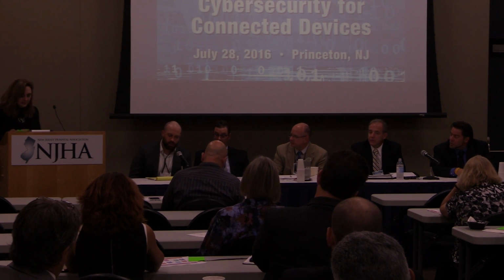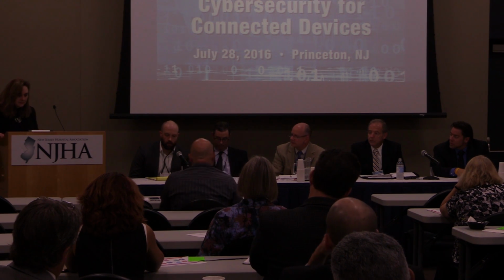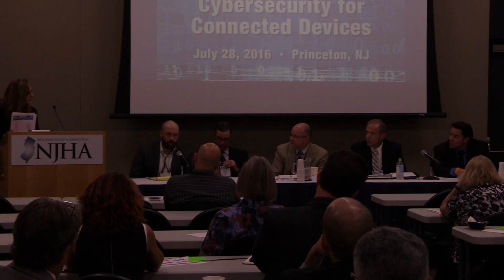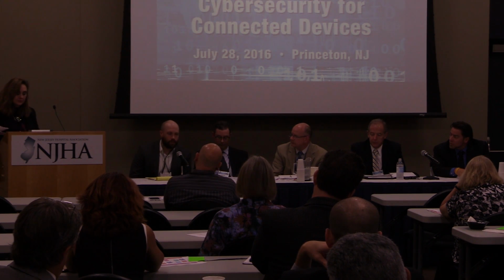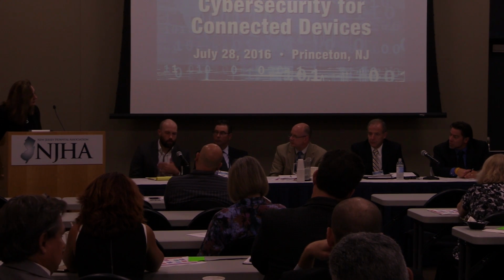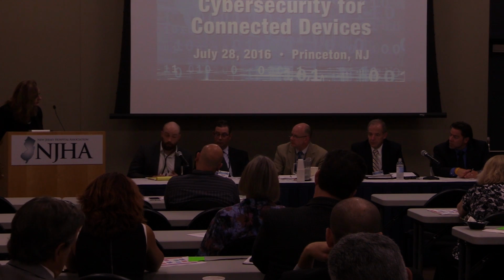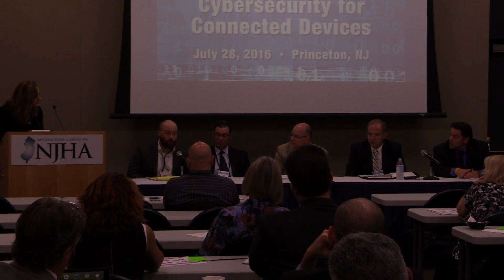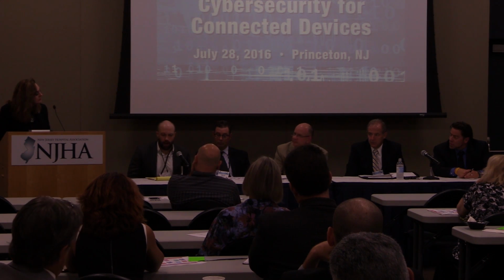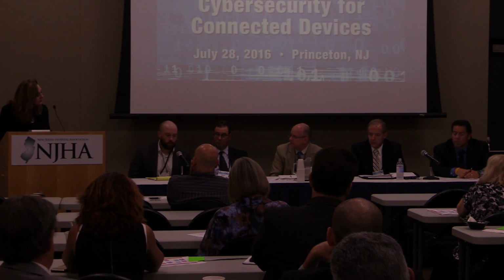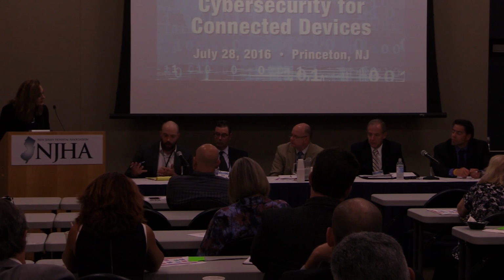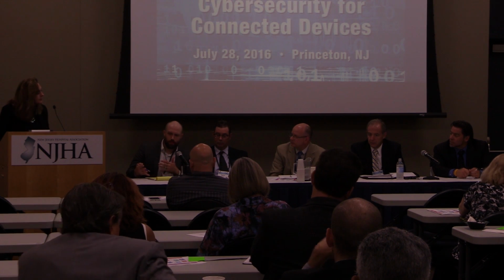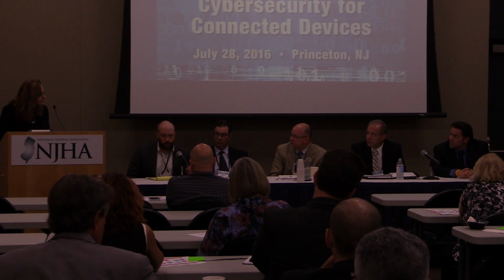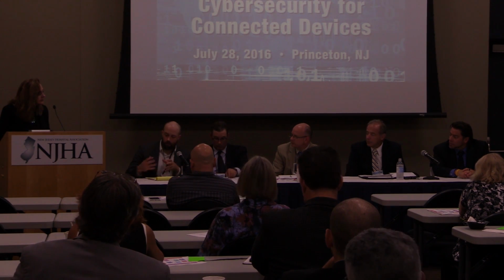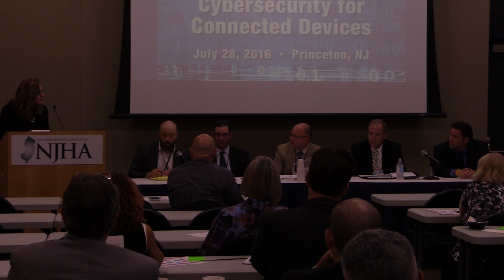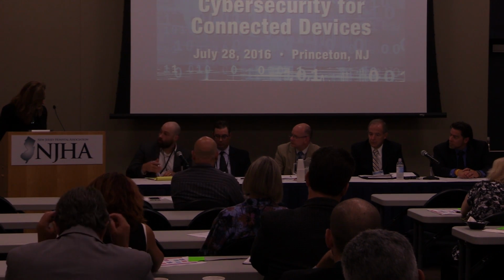If a manufacturer doesn't identify that encryption is necessary, a reviewer would never say, keep people from using encryption. They would come and say, okay, I see in your risk analysis you're sending PHI, there are HIPAA-related questions here. How are you protecting the data? That's the type of question that would be asked, so at the review level, not necessarily at an audit level. So the concepts like, oh, FDA wouldn't allow that, or wouldn't ask about it, I don't understand that. Certainly the reviewer would look at the device, how it functions, and say, okay, there are risks here associated with sending data. What are you doing to control those risks?